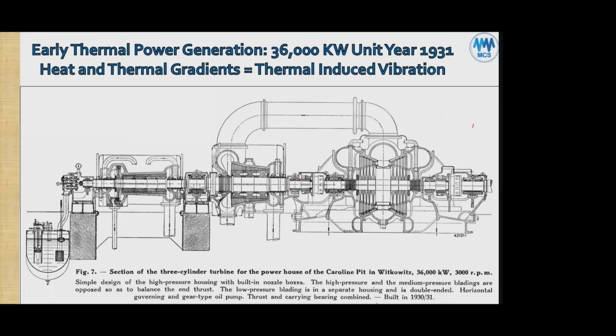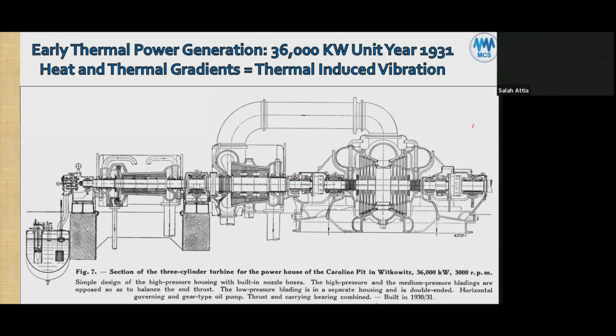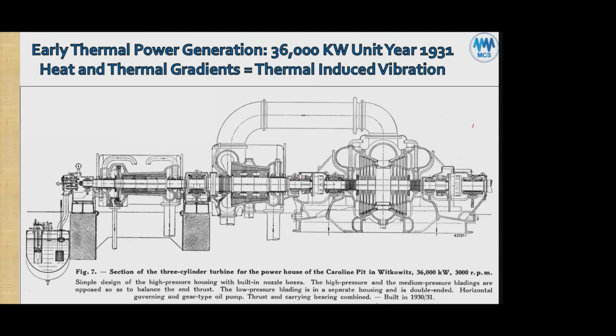in his case, he said it only happened at no load. Therefore, with load, there would be steam, but he says it happened at no load. It means it's not caused by steam whirl at all. It's not steam related. If his facts are correct, and it only happens at no load, then it's closer to what you said, that it's some kind of oil whirl. And I also add another one here is, these machines, they have vibration sources living inside them.